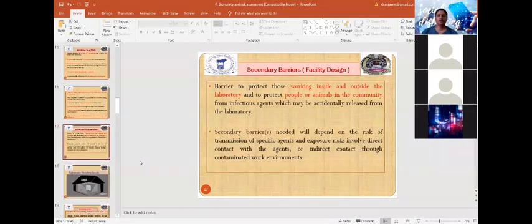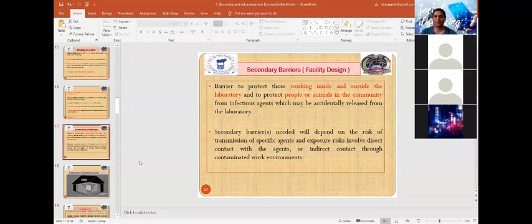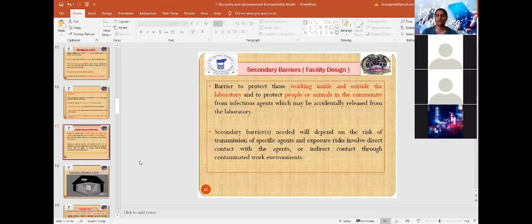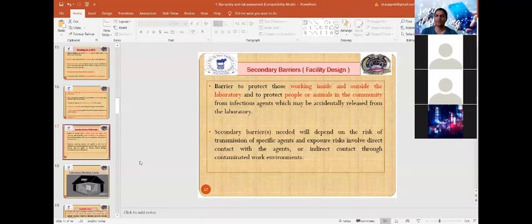Secondary barriers refer to facility designs that protect those working inside and outside the laboratory, as well as the community and environment, from infectious agents that may accidentally be released from the laboratory. The level of secondary barrier required depends upon the risk of transmission of the specific agents.